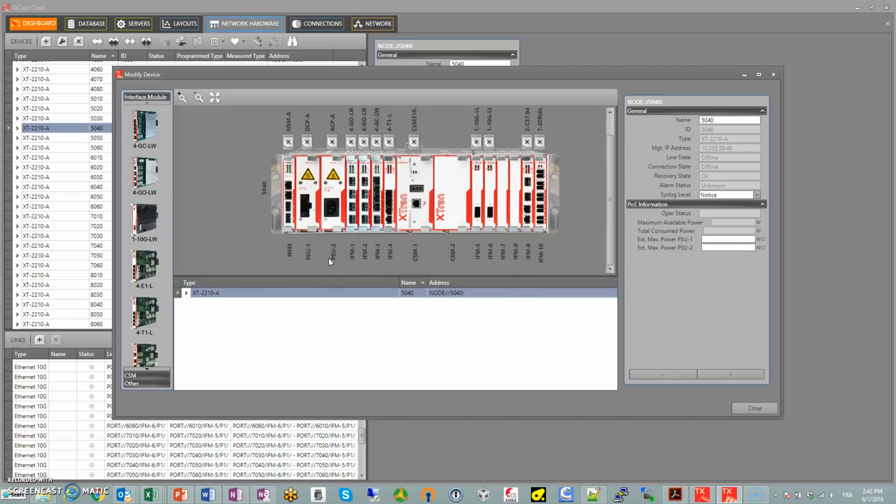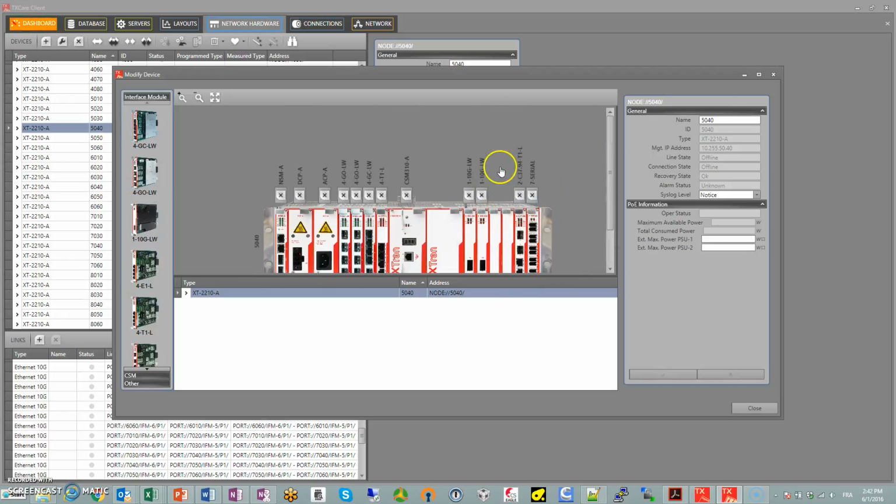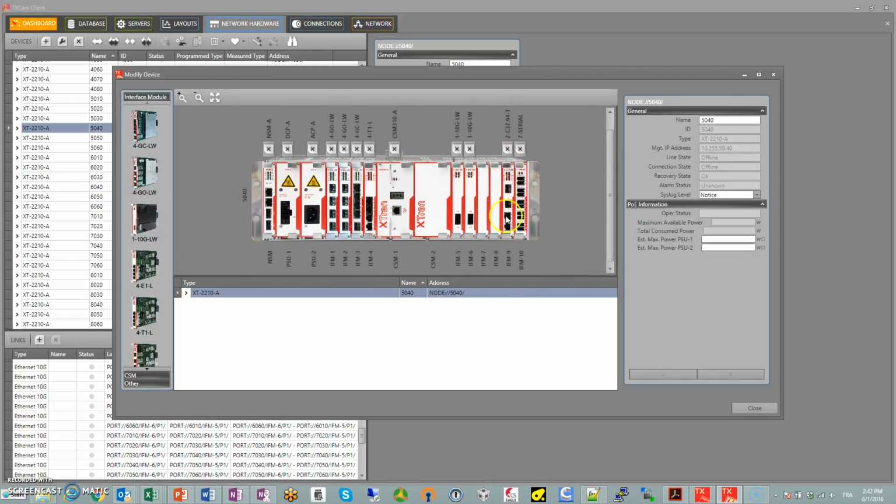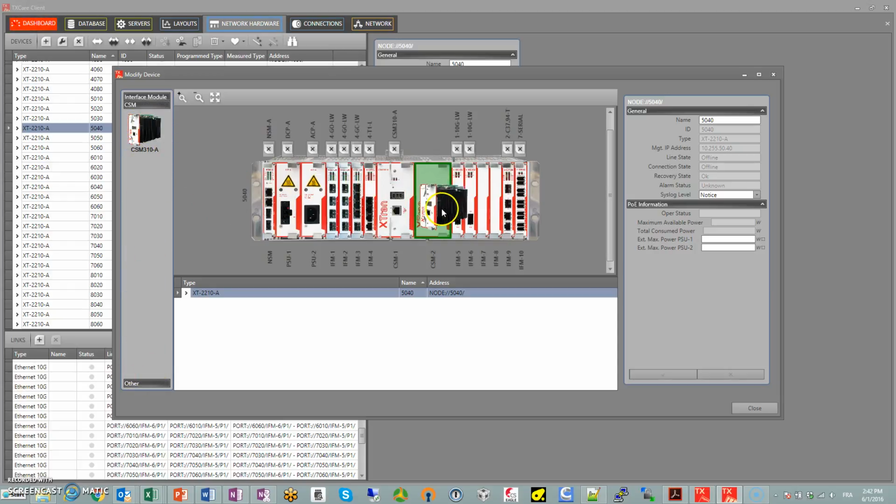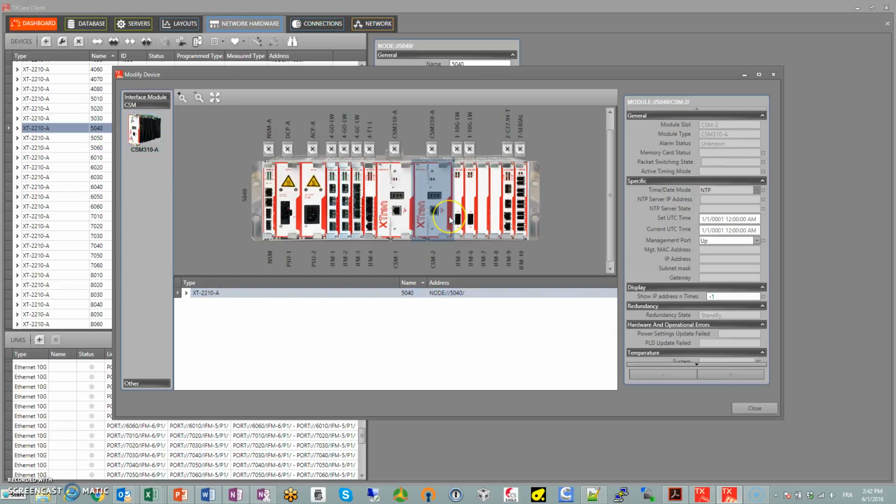This is what it looks like. It does have the C37.94 module inside of it, but it doesn't have a redundant core switching fabric. So we're going to add this core switching fabric right here. And obviously by doing this, it's not physically adding it out in the site, but it's provisioning it. If the module is not inserted, I will see this in my alarm, because I'll have a mismatch between what I have configured and what's actually physically out there.